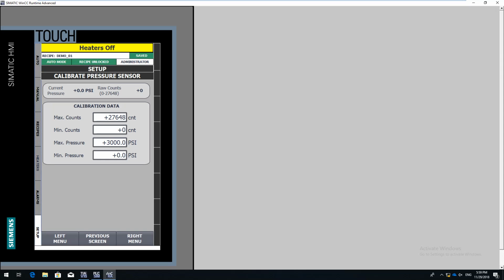The calibrating the pressure sensor, same concept, but pressure sensors, at least the GEMS pressure sensors we're using in the machines, are already calibrated from the factory of 0 to 3,000 psi, and it's translating to 0 to 10 volts, which is also the 0 to 27,648. It's already scaled from the factory. I don't need to do anything. I just type in my values right here, and everything's taken care of. There really should be no reason in the field you need to readjust these values.